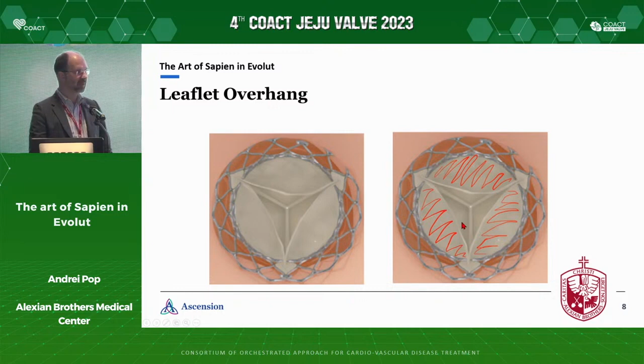So this is comparing two papers from the same group in Vancouver, showing you the outer diameter measurement of an Evolut valve in which you put a Sapien valve. What's interesting is, comparing the two papers from the same group, when they measure the outer diameter of the Sapien valve, that diameter is actually larger than what they're getting for the Evolut valve. That's important because it tells you that the frame of the Evolut constricts the Sapien valve a little bit and doesn't allow it to open fully.